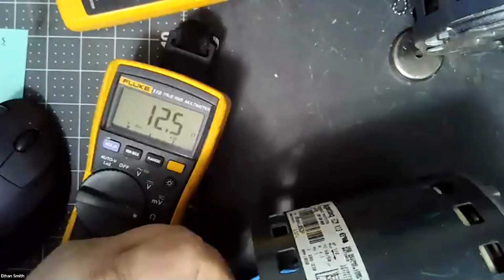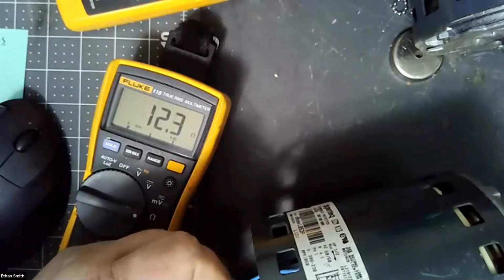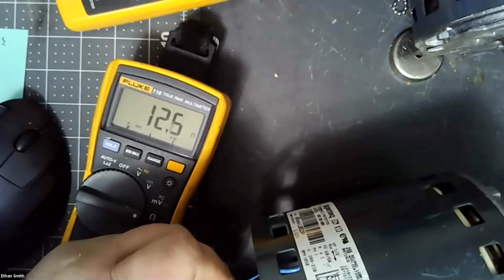But you'll notice if I get loose here and I start moving my probes around, okay, I'm still on that pad. But as I move it around, my number goes all over the place. Okay. So yeah, I sat there for a while and tried to make sure I was getting good connection on it, but it was bouncing quite a bit. So I bet you that wire connection in between there was kind of off and on.